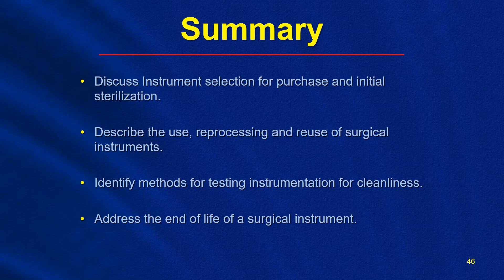The first one is, how can my OR staff be sure that instruments are sterile before using them on a patient? All right, so you're opening an instrument tray and your staff's wondering, how do I know these are sterile? Well, there's several ways. Clearly, there needs to be an indicator inside the tray that has changed to show that it has been subjected to the proper temperature and steam for an autoclave. You need to look at the tray lids to make sure that they're intact.